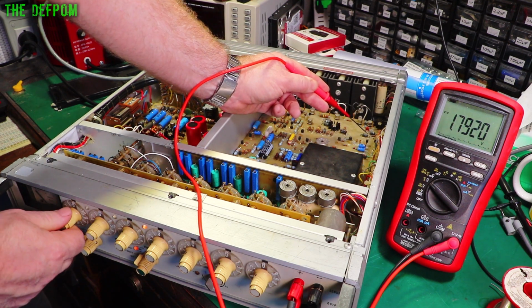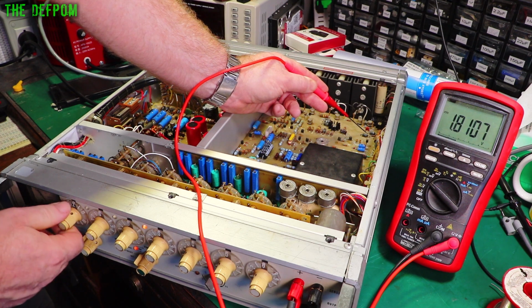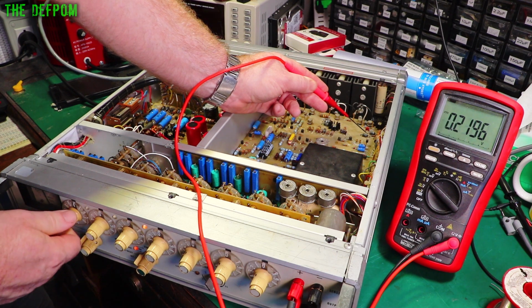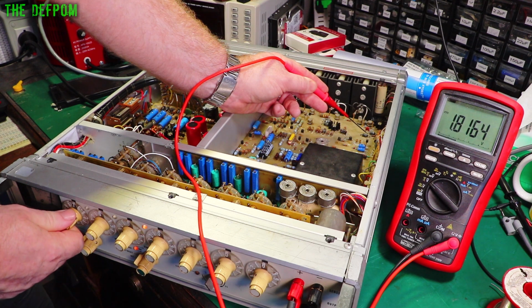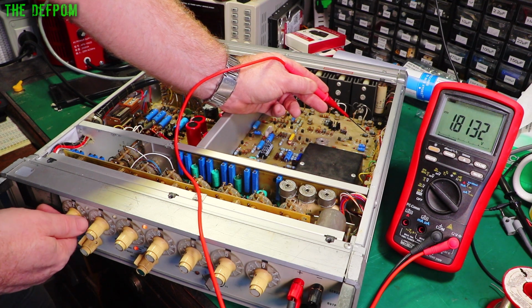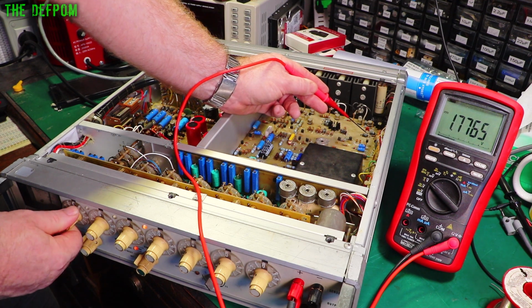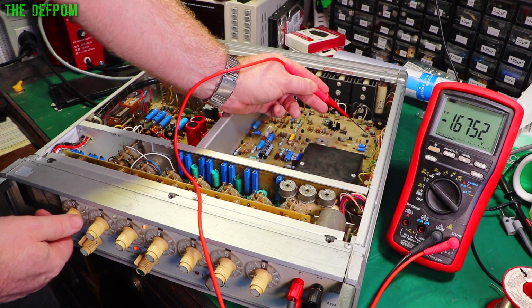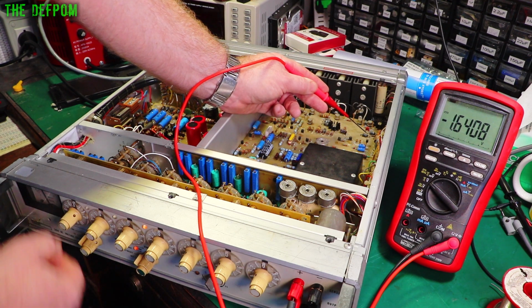Right, so if I just go through at 0 to 100, 200, 300, negative voltage, 400, 500, 600, 700, 800, 900 and 1000. You can see they're basically all very similar voltages. It does step up as it goes through the levels depending on which tappings it's using on the transformer. But the one which is completely different is the 300 volt range. So this is obviously either a correction voltage or some kind of fault. I'm guessing it's a correction voltage. So I need to trace back from here.